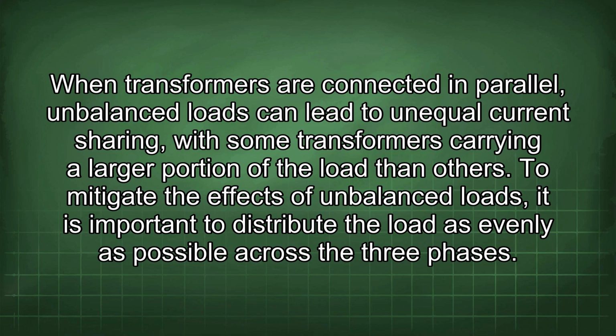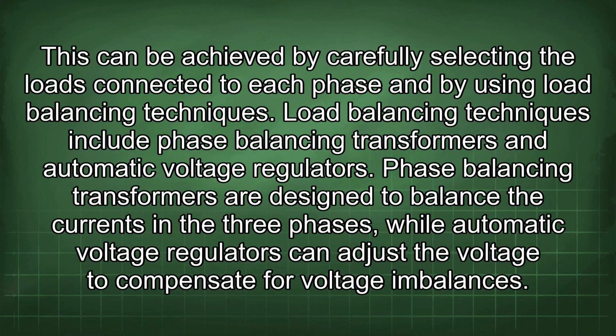To mitigate the effects of unbalanced loads, it is important to distribute the load as evenly as possible across the 3 phases. This can be achieved by carefully selecting the loads connected to each phase and by using load balancing techniques. Load balancing techniques include phase balancing transformers and automatic voltage regulators. Phase balancing transformers are designed to balance the currents in the 3 phases, while automatic voltage regulators can adjust the voltage to compensate for voltage imbalances.